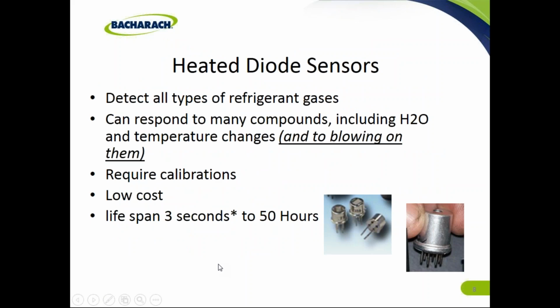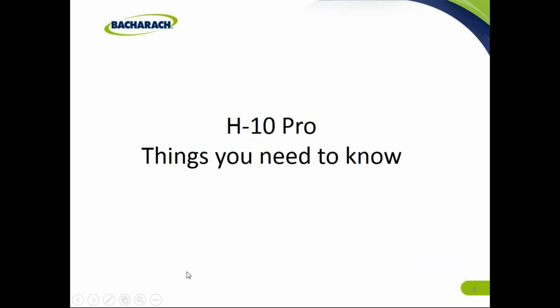So heated diode sensors in general detect all types of refrigerants. They can respond to many compounds, including water and temperature changes, like blowing on it, because of the moisture in your breath and the change in temperature in your breath. They require calibrations. They're low cost, and they can last 3 seconds to 50 to 100 hours, depending on how much gas they see.